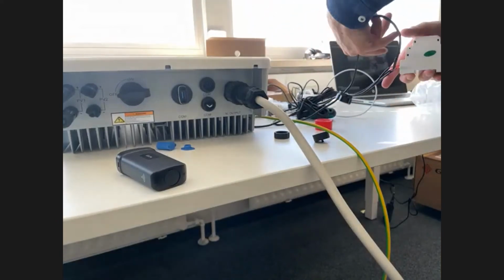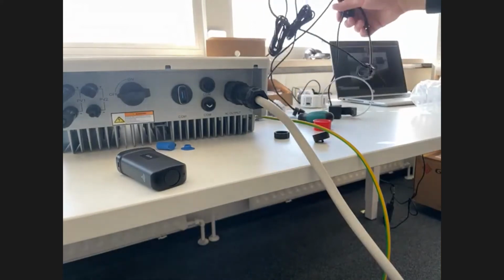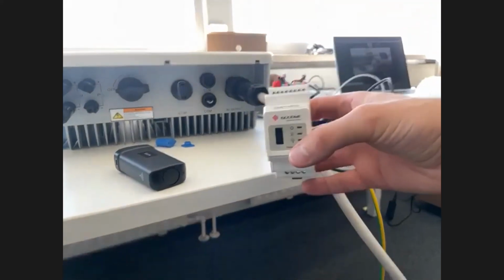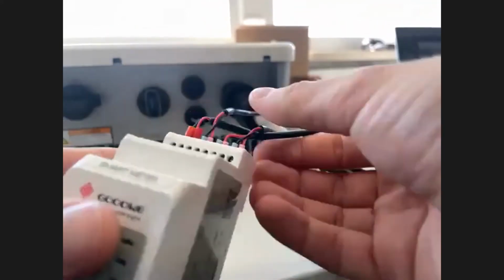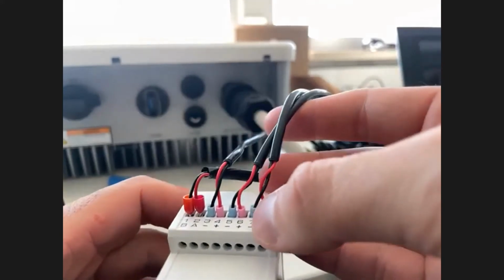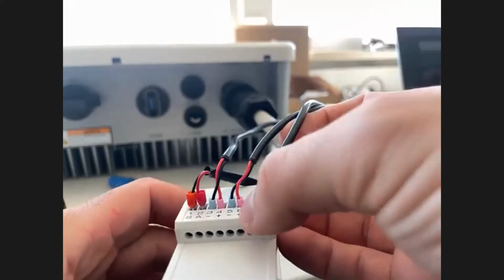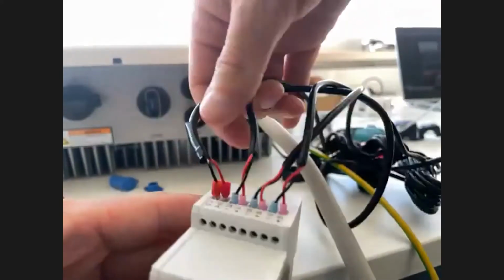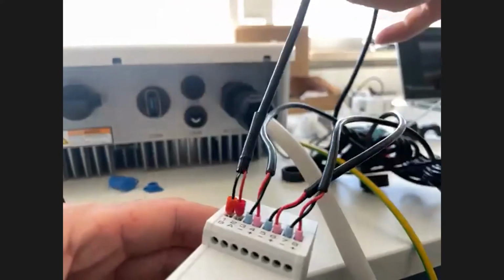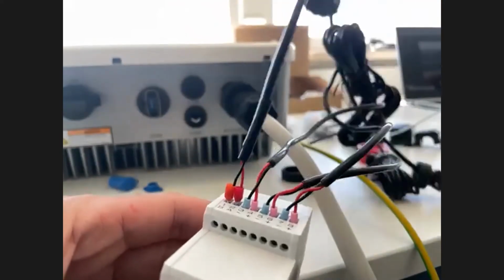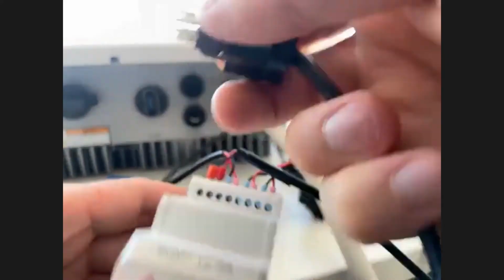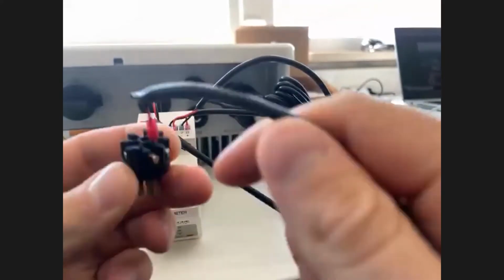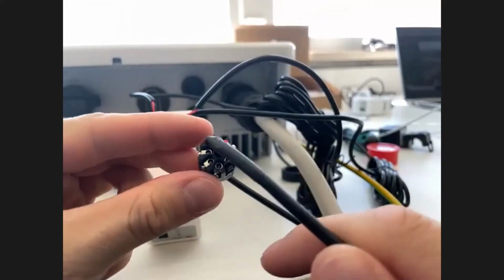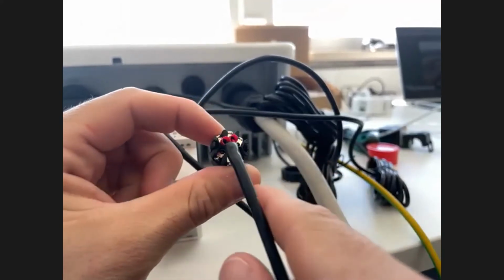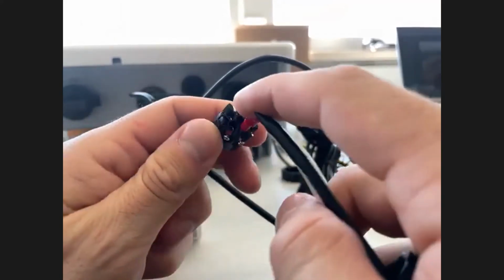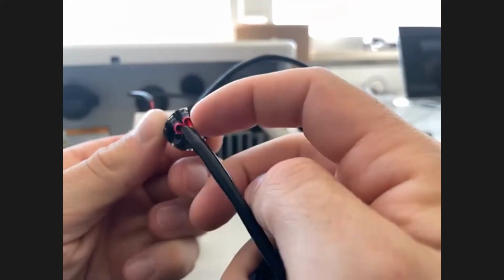I will show here how I have done it. So here you see the smart meter with each connected CT. So you have the plus and the minus of 1 CT, the plus and minus of the 2nd CT and the 3rd CT. And here on the end, you have a normal RJ45 cable. Basically just here, the cable, and then on the other side, on the inverter, there is a little thing that comes in the box. And here you see the different pins that I showed you in the presentation. So you have the 1, 2, 3, 4, and the last two is the 5 and the 6.